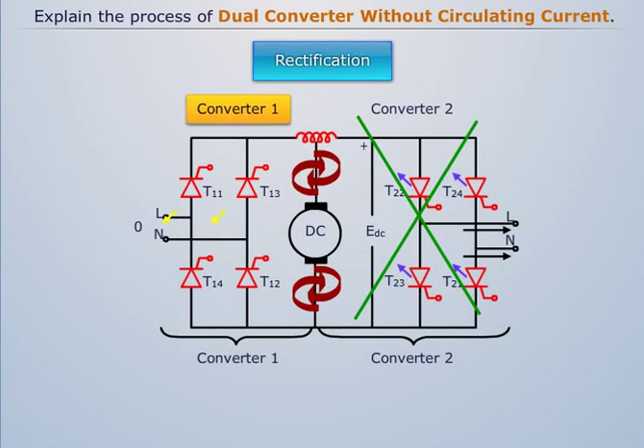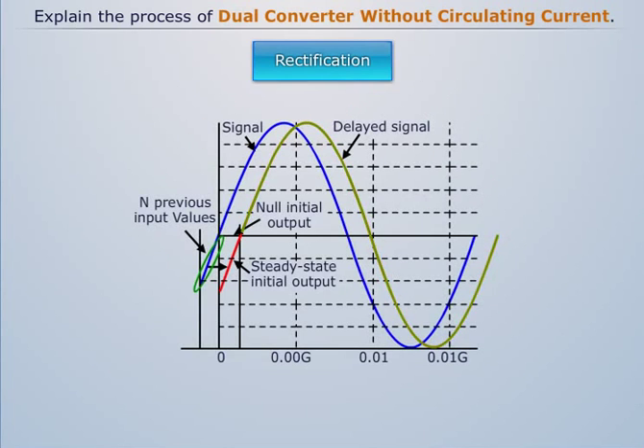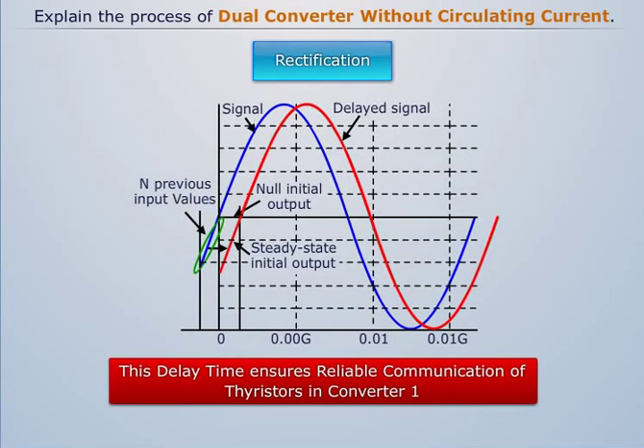And similarly in rectification mode, converter 1 will supply the load current, while pulses to second converter are blocked. And the pulses to converter 2 are applied after a delay time of 10 to 20 ms. This delay time ensures reliable commutation of thyristors in converter 1.